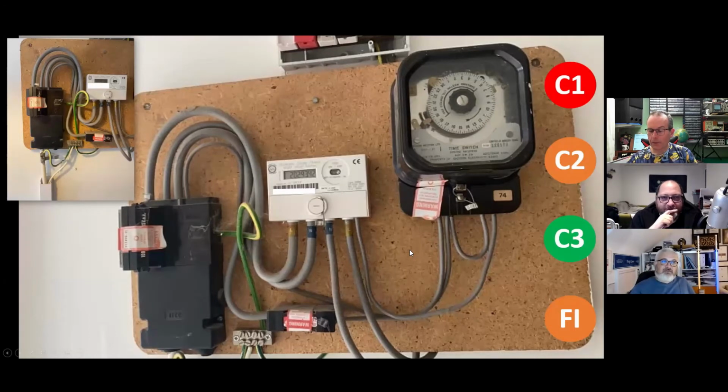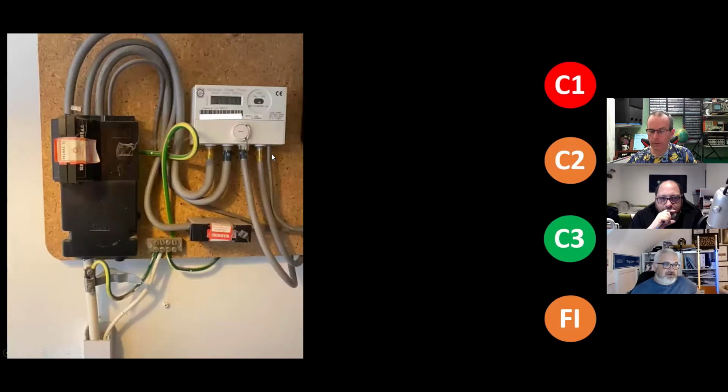This is a cracking photo. If anybody wants these pictures or presentation, let us know and you can have them. And there you go, there's it a little bit clearer. You can see there's a conductor. You can see the clamp on the cable. I personally think an electrician's put that clamp on. Doesn't look like a DNO have done it.